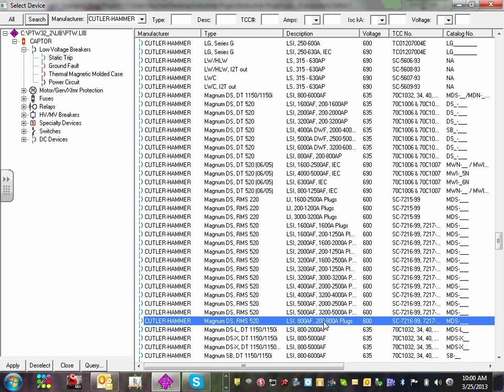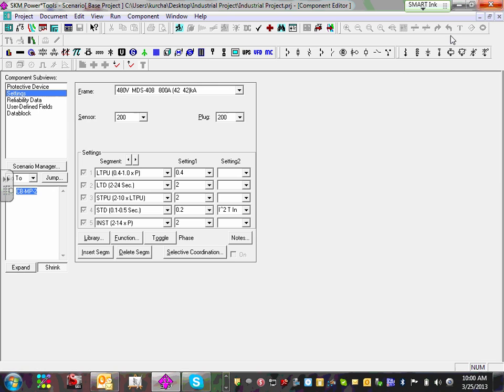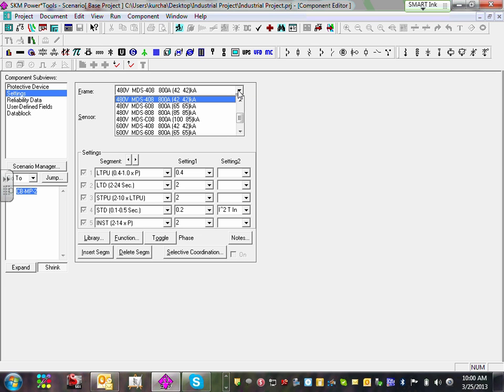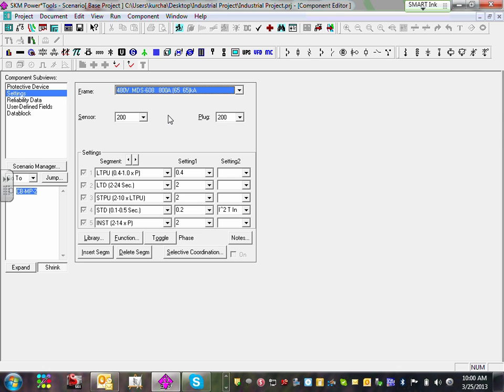Okay, double click on that one. When you double click on it, you load it. Now I want to quickly remind you, if you click on that one with an 800 amp that has 480, pick the one that has a 65K interrupting rating. Can you see that? The top 480V MDS-608, 800 amp, 65 - that gives you more interrupting rating. Grab that one first because there's a family, the frame.